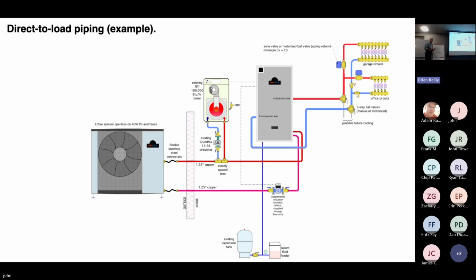We run that entire system on a single Taco 0018 at full speed. It draws 44 watts. At partial load, it's running on about 25 watts, delivering about 36,000 BTUs per hour, which is the design load. But every one of those radiators is a zone because it has a separate valve on it.